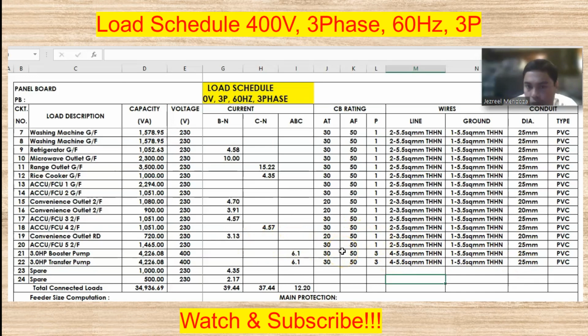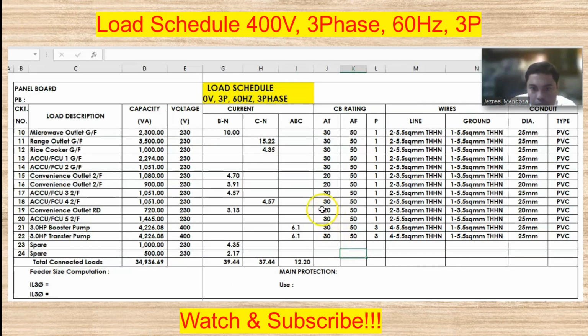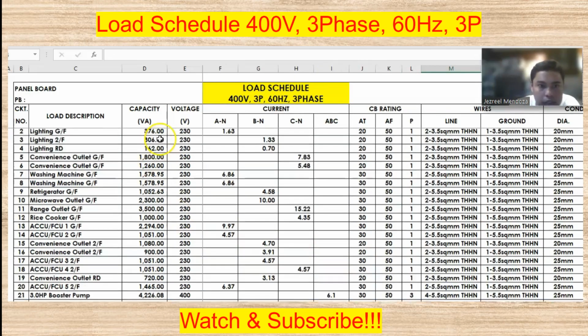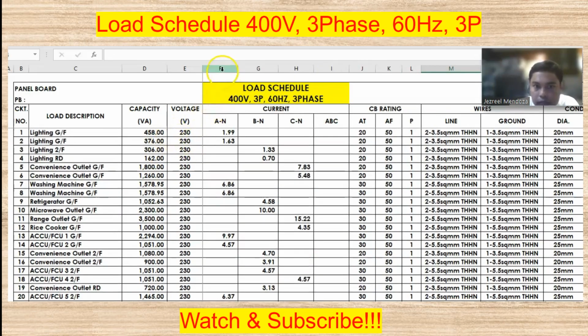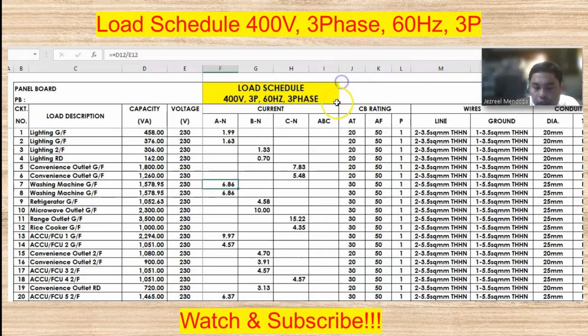For the spare and space, we can use this 30 amperes or even this 20 ampere circuit breaker. That is for reserve yung spare natin. So we're done on the load balancing, done on protection, we're done on the wires, so on for the conduit. So next is we need to determine what is the main size of the circuit breaker.